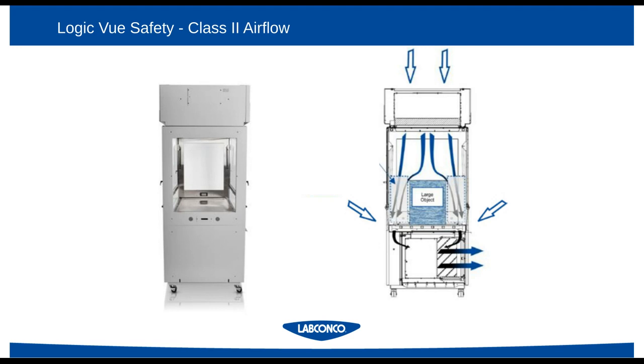So looking at the airflow, just representing how airflow is moving through this design, the air is entering through the top of the enclosure for the supply HEPA filter and pushing down through the work surface after being passed through HEPA filters. On the left and right side of the unit, there are inflow arrows, and those are the protective airflows that keep users safe during operation. This unit has an 8-inch sash opening that runs the full width of the instrument to allow for full access to all of the parts of the instrument during use.